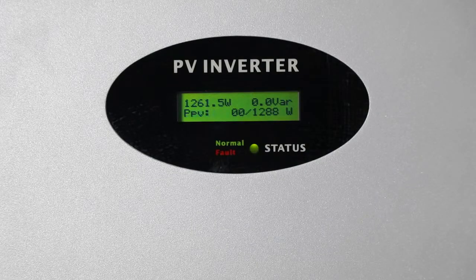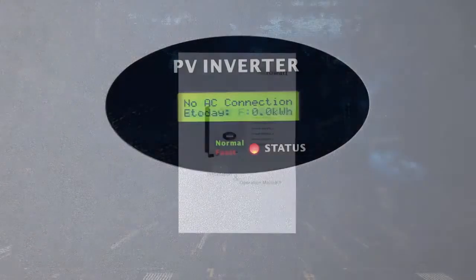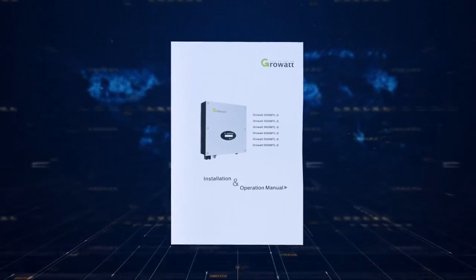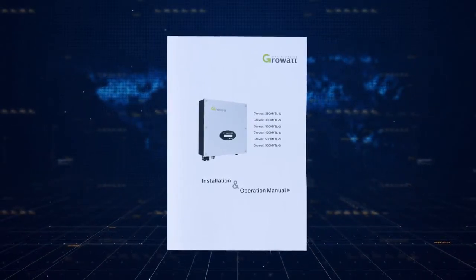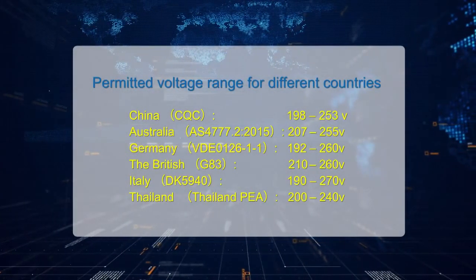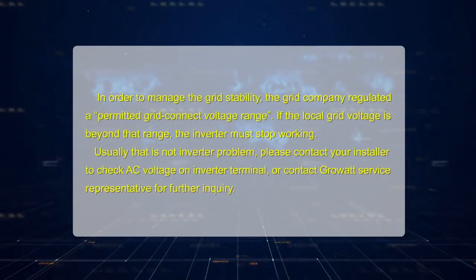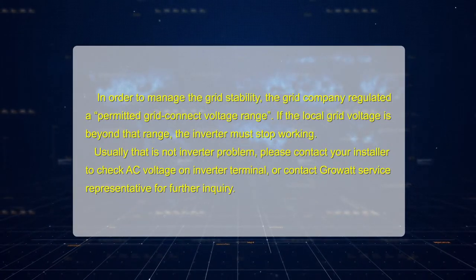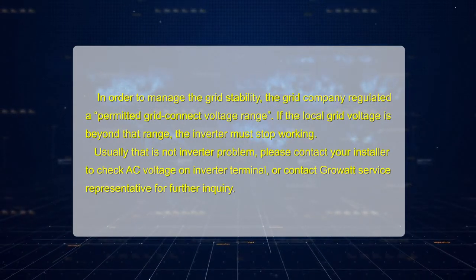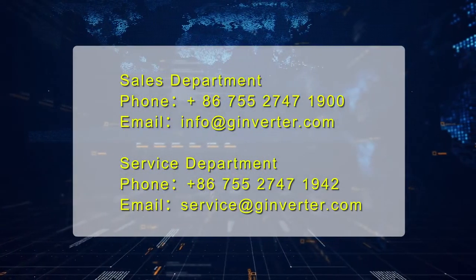The inverter will show an error message or error code on its LCD screen if a fault occurs. Please refer to the user manual for a complete fault list and descriptions. There is also a detailed troubleshooting guide available on the Growatt website. In order to manage grid stability, grid companies regulate a permitted grid-connected voltage range. If the local grid voltage is beyond that range, the inverter must stop working. Usually, that is not an inverter problem. Please contact your installer to check the AC voltage on the inverter terminal, or contact a Growatt service representative for further inquiry.